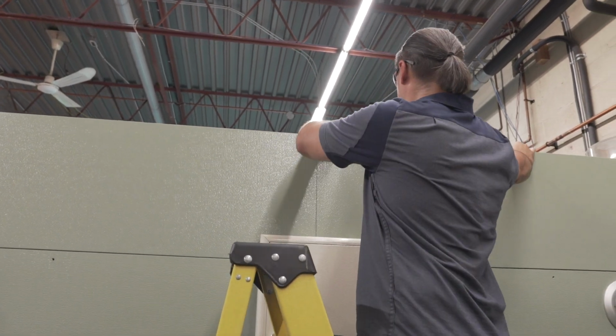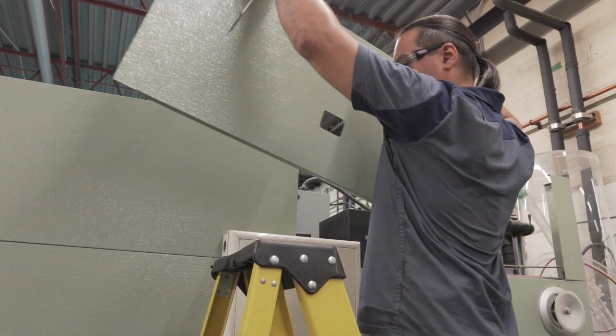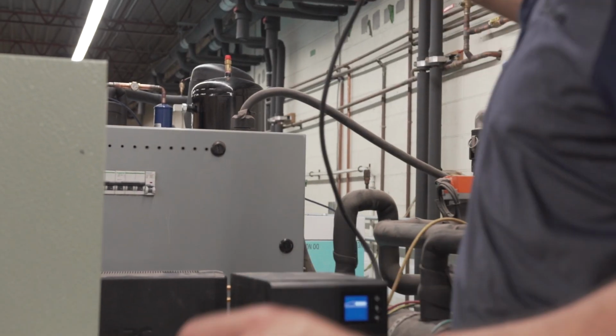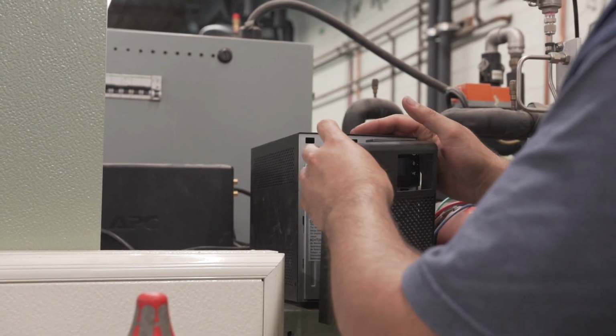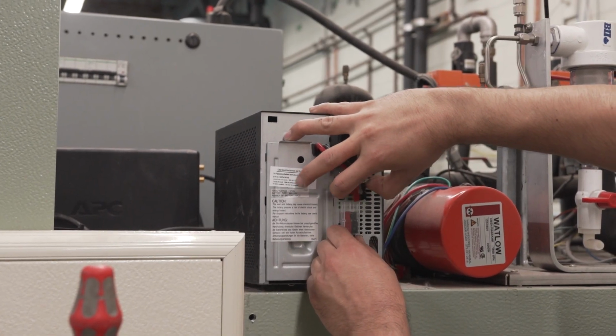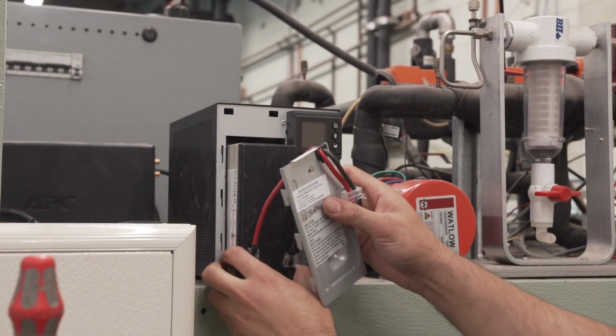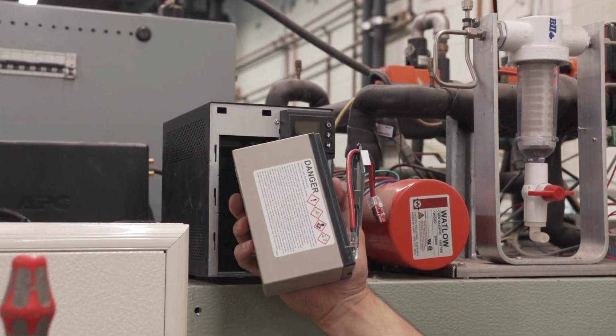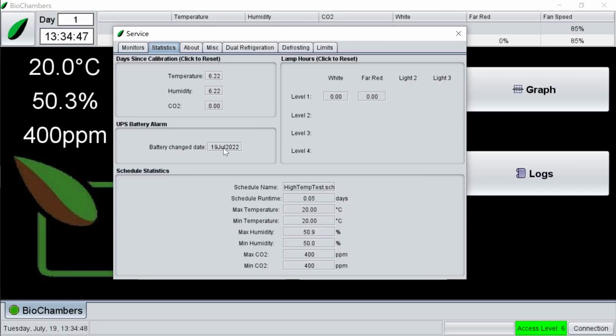Finally, replace the battery in the uninterruptible power supply, UPS, for your chamber's control system every 2 to 3 years, depending on which UPS your chamber has. Turn off and unplug the UPS from its power source, and then follow the manufacturer's instructions on how to replace the battery. Equipment with newer versions of VNet software have a battery maintenance alarm, which will trigger when it's time to change your UPS battery. After reconnecting the UPS with the new battery, reset the battery change date alarm by clicking here in the Statistics tab of the service area of VNet.